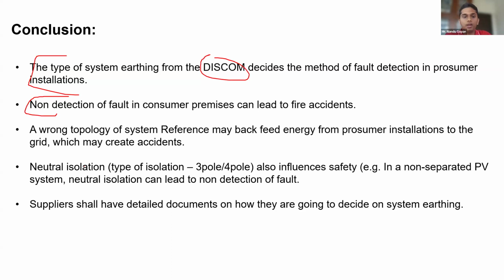then the detection of fault as per the topologies won't be done. And in some cases, for suppose for a functionally earthed system topology, instead of separating the neutral, as you are supposed to, if you have not separated the neutral and you have only separated the three phase conductors, then also there will be a problem. So this is what is there in the third point. So system isolation should also be looked into really, really carefully.